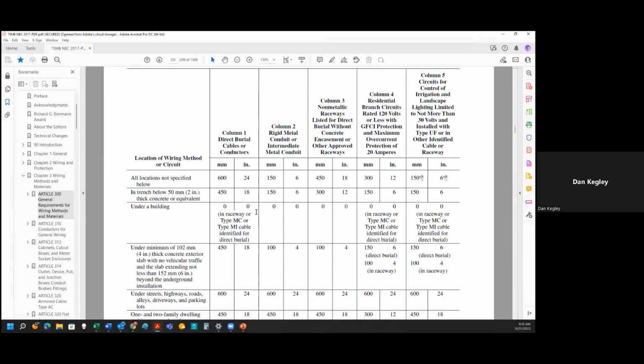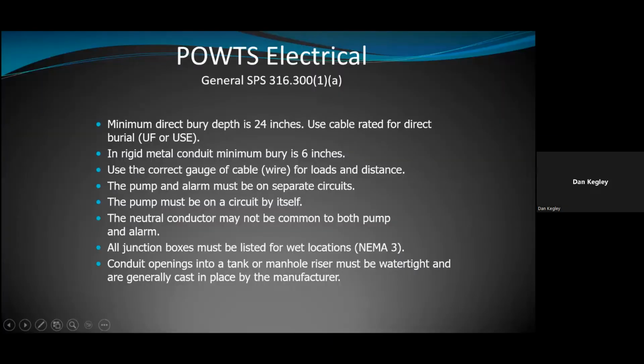So, get back to here. The chart in the slides that says how deep it should be really doesn't apply because everything can vary so much. But I think the key is if you're in a residential scenario, it's 18 inches across the board. That's the key thing. Like I say, if you're not at a residential facility and you're not sure, 24 inches is the when-in-doubt number. However, there are exceptions to go less if you follow the chart.